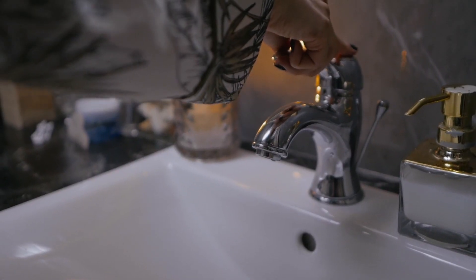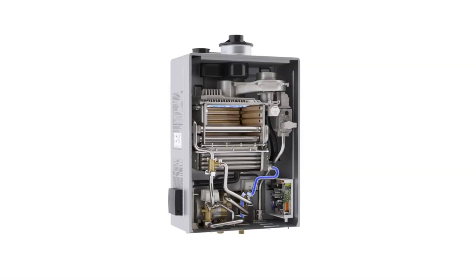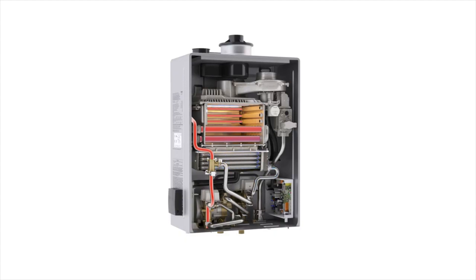But let's say you have a tankless system instead. Here's how that works. You turn on the hot water tap in your shower. In your mechanical room, cold water will start to enter the heater. A flame ignites and heats the two heat exchangers that are located in the heater, and the cold water makes its way through those heat exchangers, absorbing heat. The heater will also adjust the flame output up or down to make sure that the water coming out is exactly what you asked for — not too hot, not too cold, just the way you want. The water then leaves the heat exchanger, leaves the heater, and makes its way to your tap or wherever you happen to be using hot water. Once you're done, the water leaves the unit, the flame turns off, and the unit goes into standby mode.